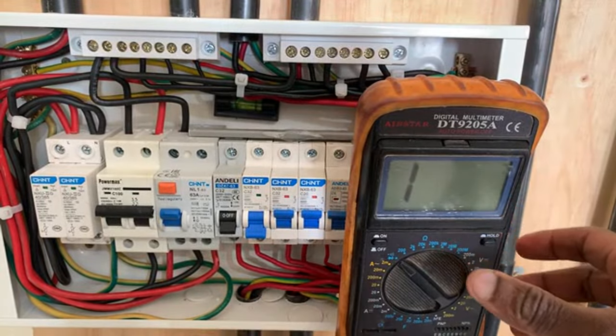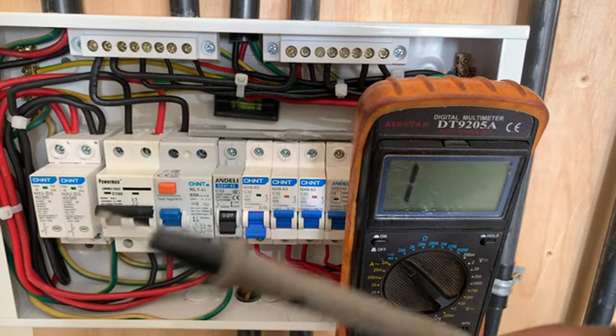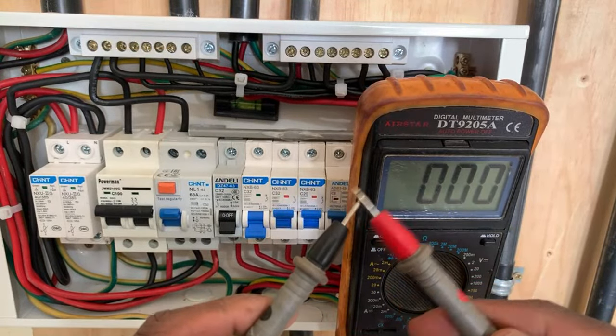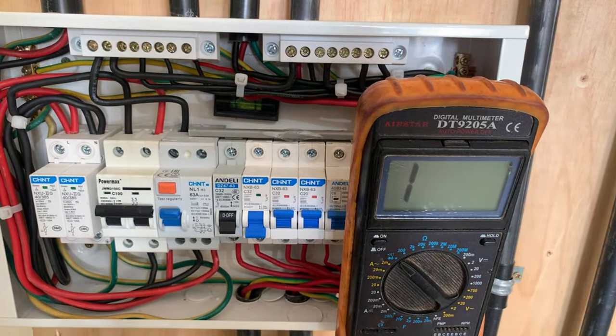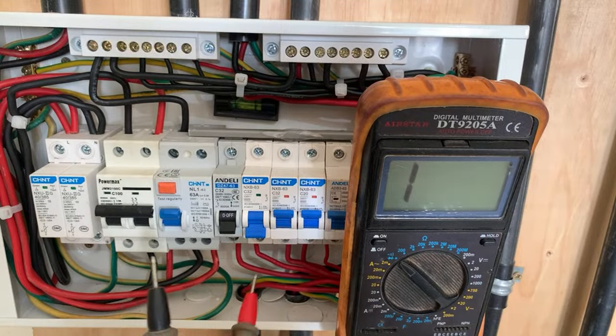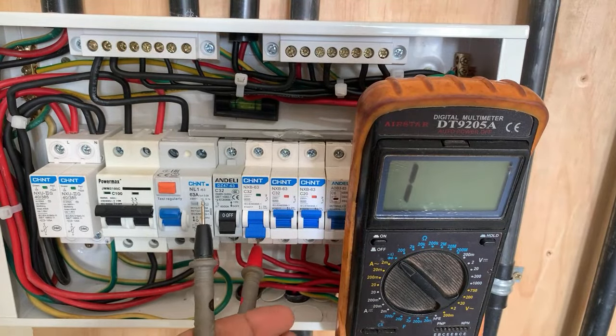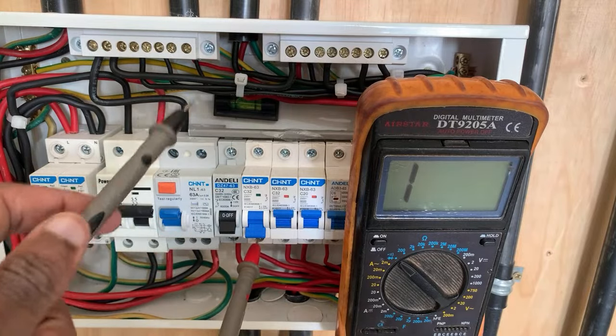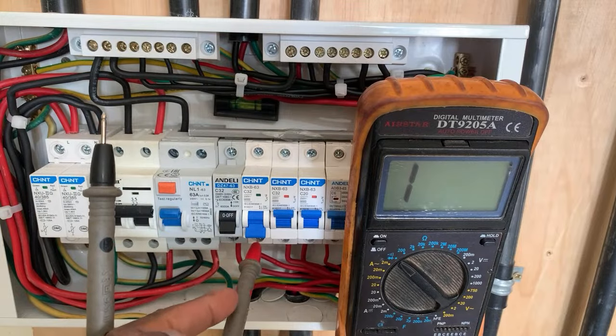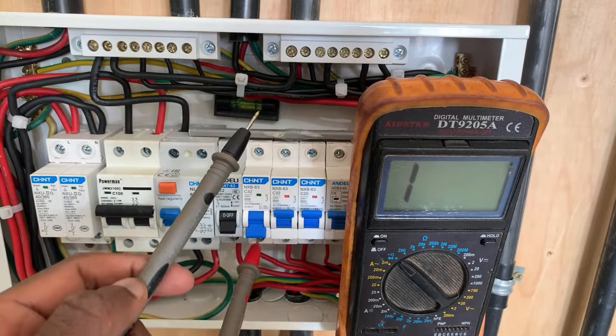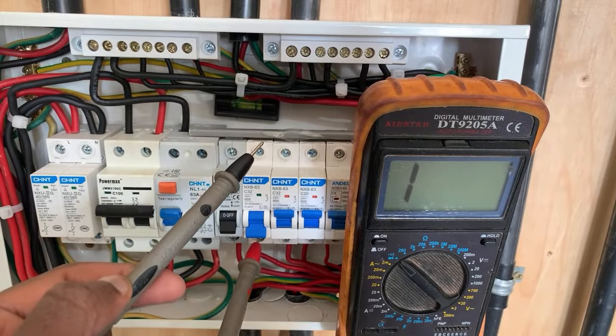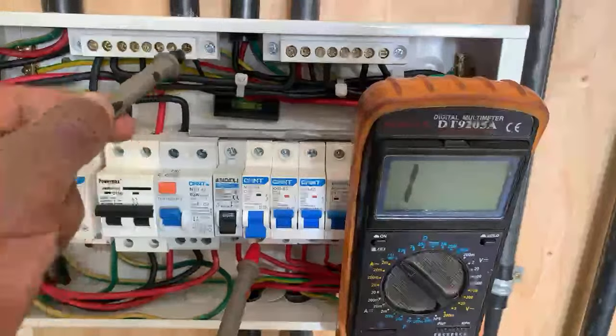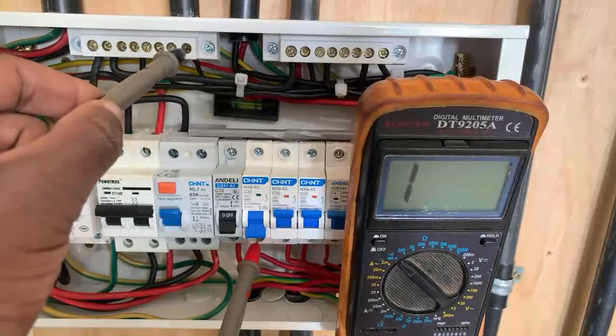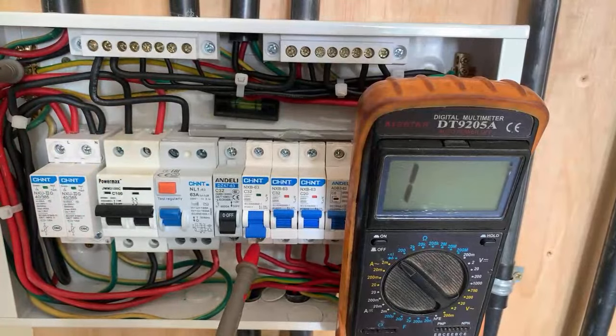Once you have your meter there, all you need to do is to take your probes. These are your probes. When you short circuit the probes, there's that sound and there's 00 on the screen, meaning there is a short circuit. And then you take your probe on this lower side where you have the output of that specific MCB. You place one probe there, regardless of whether it's the black or the red. What we are looking for is if the circuit has an issue. Then you plug it on the neutral. There is no problem. You plug it on the earth connection there. There is no problem.